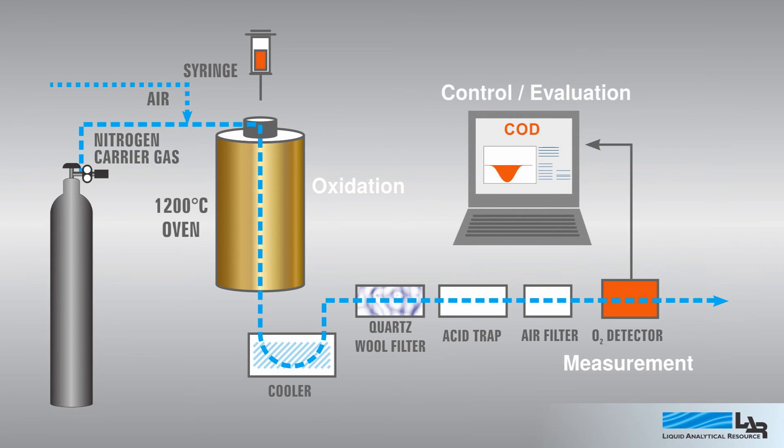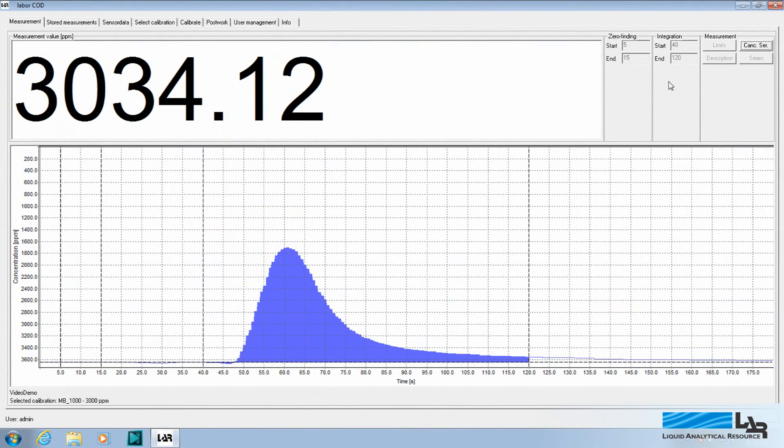As the gas passes through the O2 detector, the measurement is transferred to a Windows PC where software inverts the negative oxygen depletion curve to display a positive oxygen demand curve. The total area within the curve is calculated to provide a complete TOD measurement.